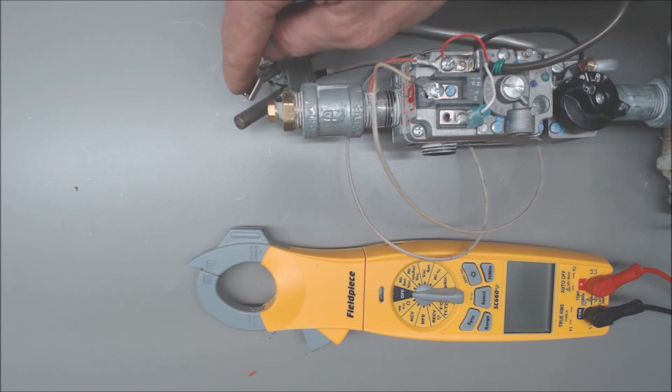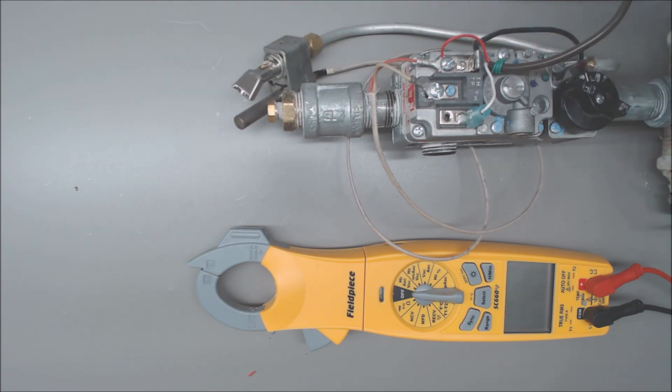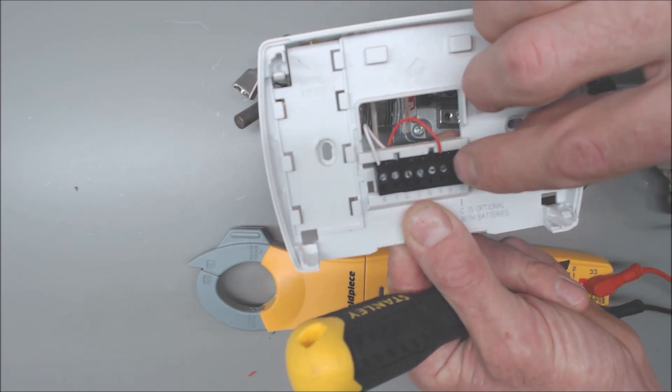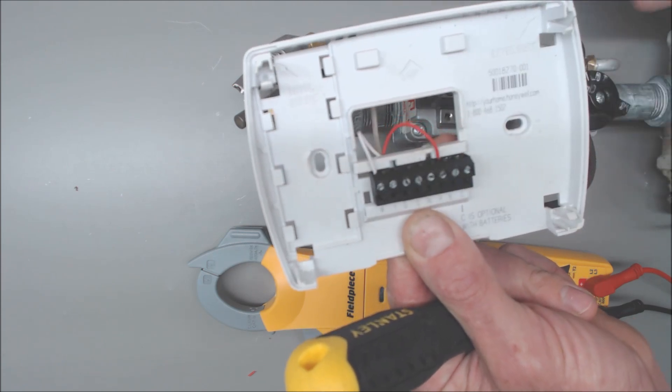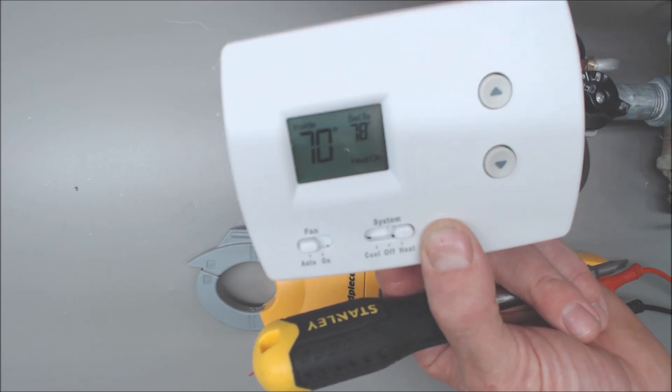Once you have your main flame and you allow about a minute for your thermopile to heat up, if you go ahead and turn your thermostat to heat by basically jumping your R to your W inside your thermostat face, you can turn it to heat and turn your temperature up.